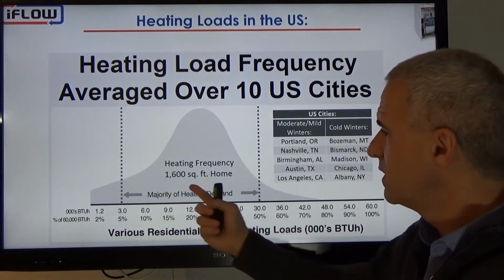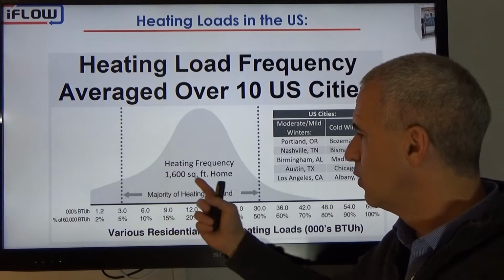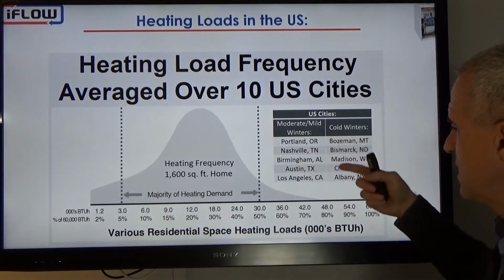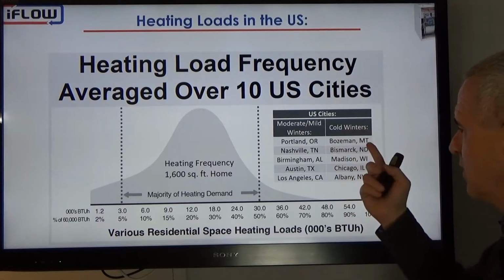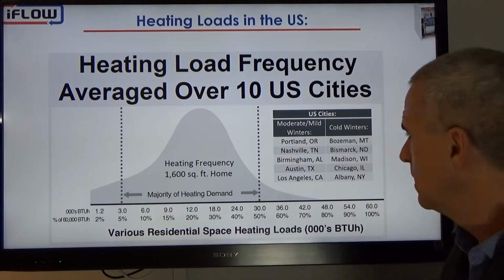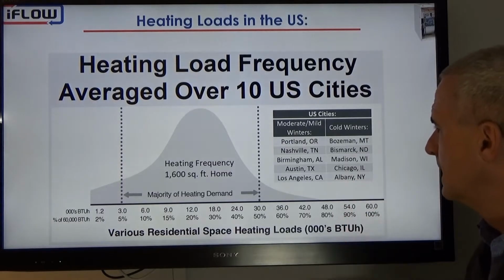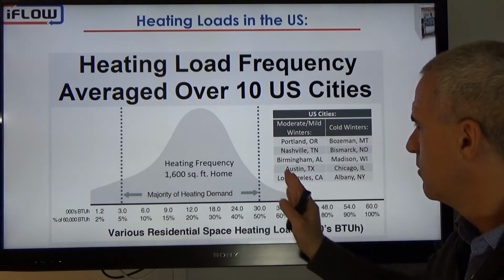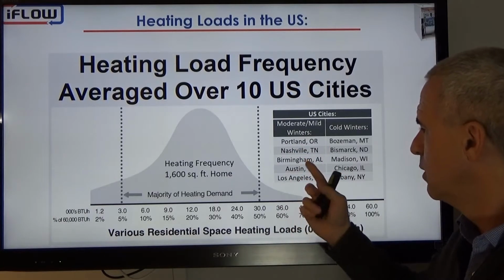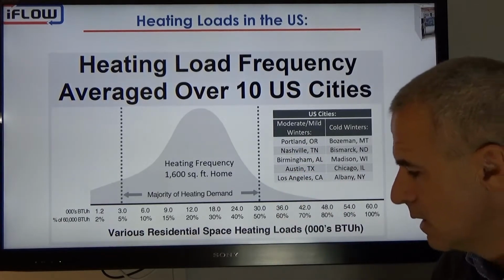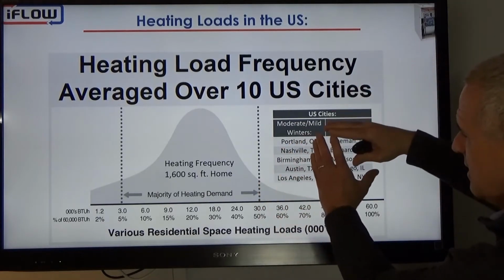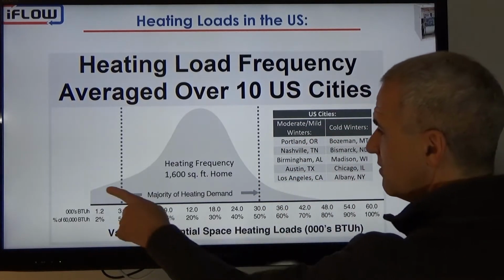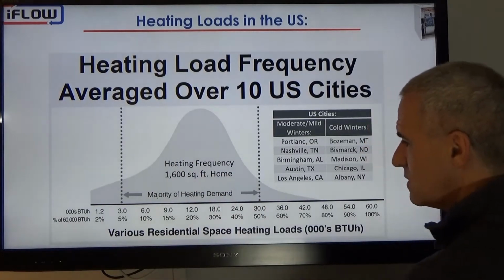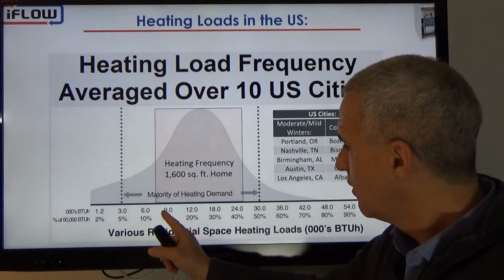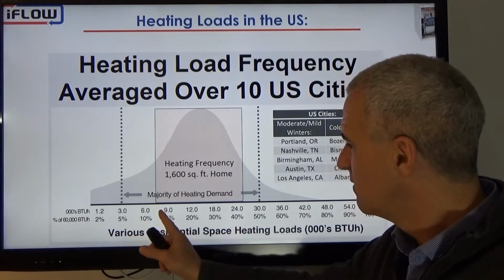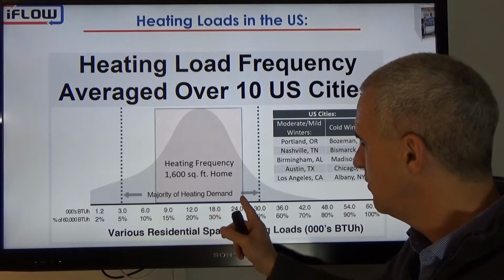So this curve is developed. This study was done on a 1,600 square foot home and modeled in 10 different cities across the US, 5 of which were quite cold. We've got Bozeman, Montana, Bismarck, North Dakota, Madison, Wisconsin, Chicago, Albany, and then offset by more moderate climates. We've got Portland, Nashville, Birmingham, Austin, Texas, and then LA. So when we average those 10 sites together, we were able to develop this curve. And funny enough, you see the majority of the heating falls in this area, between less than 9,000 BTUs up to 24,000 BTUs.